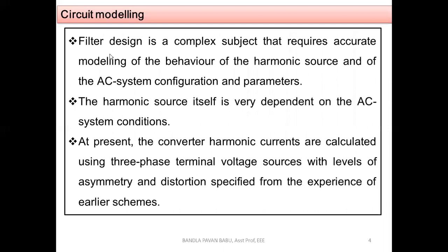The next design factor is circuit modeling. Filter design is a complex subject that requires accurate modeling of the behavior of the harmonic source and of the AC system configuration and parameters. We need to consider different types of harmonics — their orders can range from 40 to 50 or even up to 70 — along with their severity and frequency levels, which affect total harmonic distortion and voltage variations. Circuit modeling defines the exact configuration of which filter type to prefer for each harmonic order.